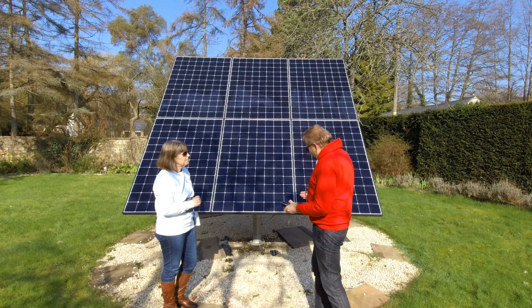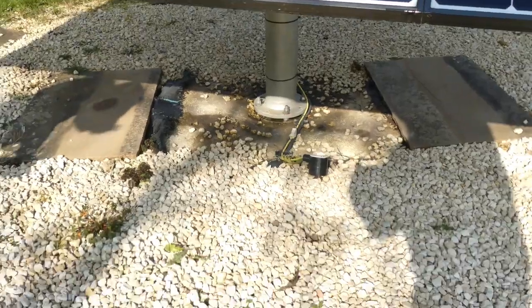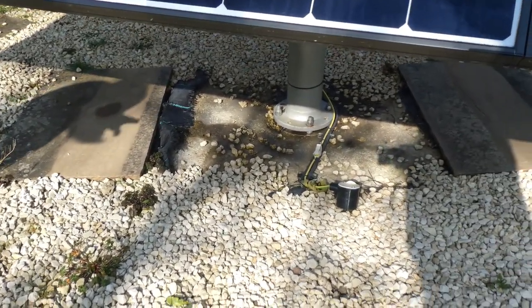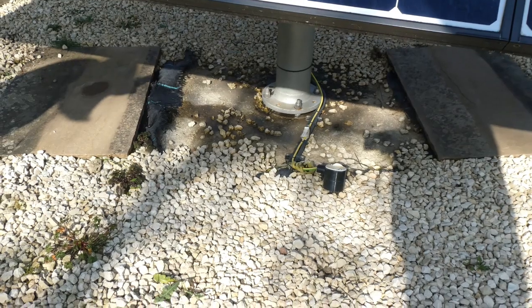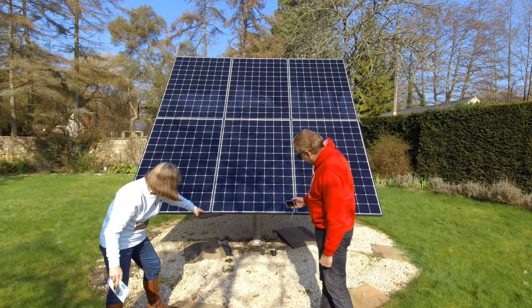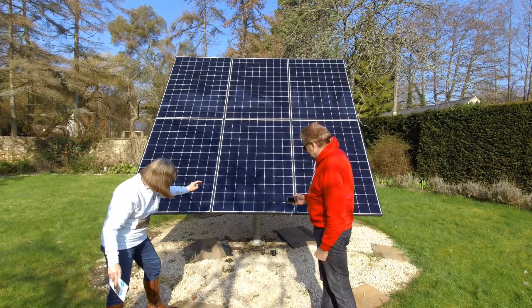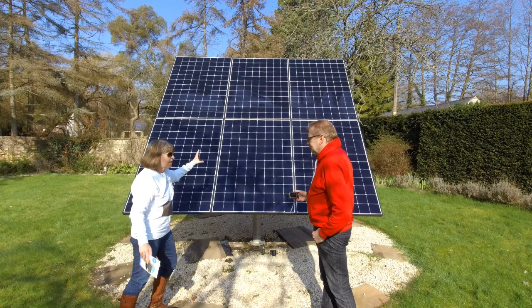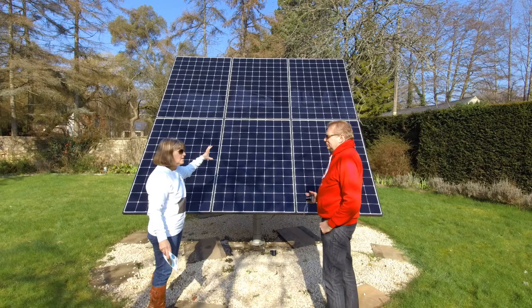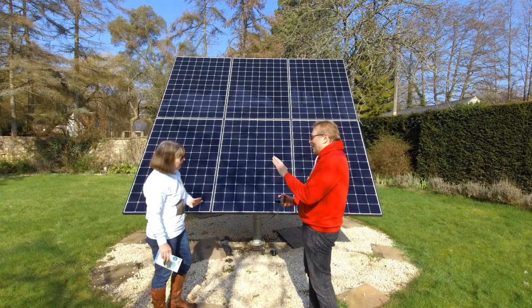In terms of installing one of these, is it a concrete pillar? Yes - it's got a metre by metre plinth in which a foundation plate is floated on the top. You can see the bolts just protruding through the foundation plate. The column bolts to the foundation plate, and then the tracking unit is on a separate piece of column which bolts on to the next bit, all held together with very serious steel bolts.